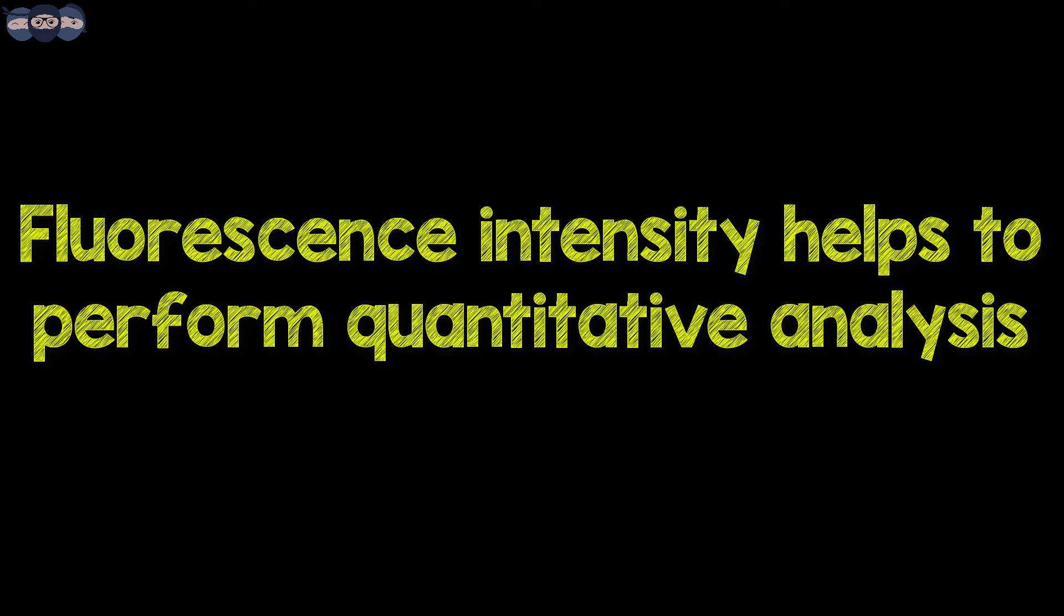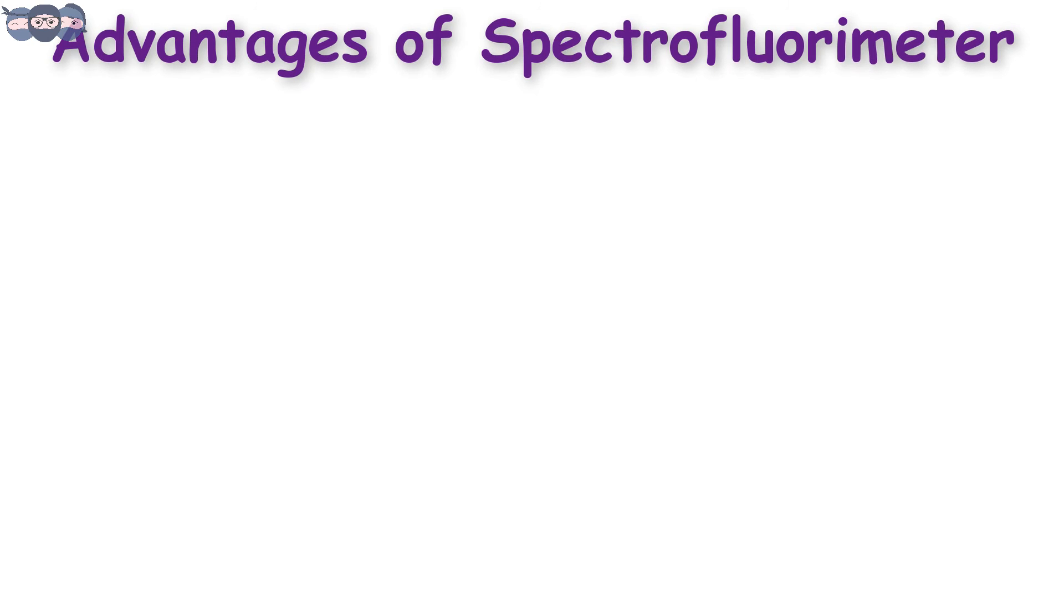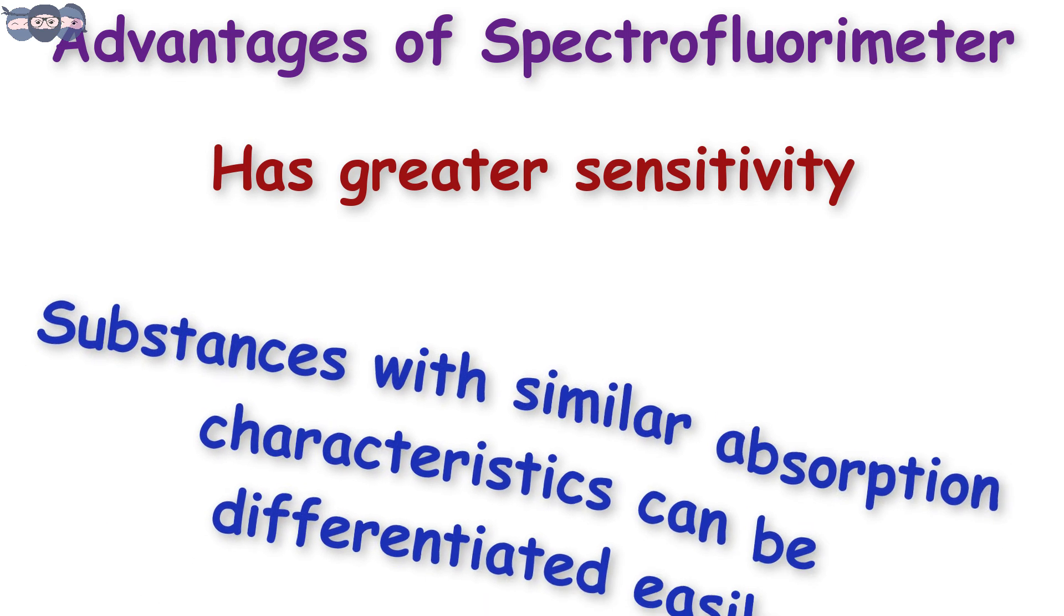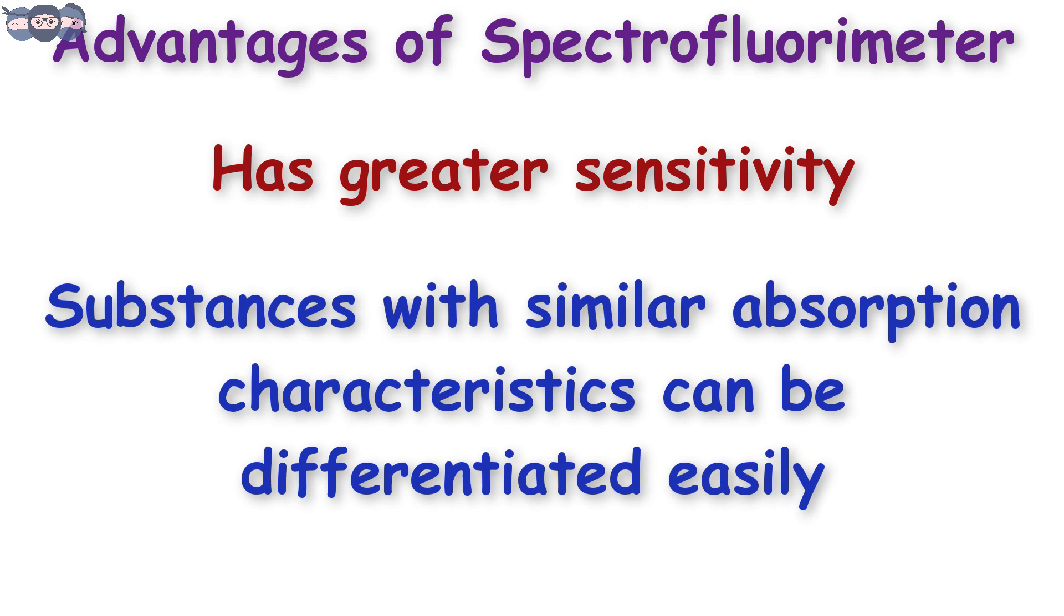The intensity of fluorescence is dependent on the number of particular molecules or electrons being present in the sample. Thus intensity helps in performing quantitative analysis of the sample. This was the working of the spectrofluorimeter. The advantage of using a spectrofluorimeter is greater sensitivity is achievable since background signal is zero when compared to absorption measurements. Differences in wavelengths between incident and emitted light help to discriminate between substances having similar absorption characteristics.